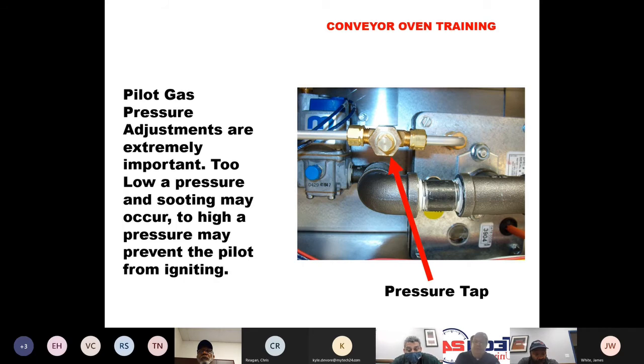Pilot gas pressure. These adjustments are very important. You're typically going to see a little T on many of the ovens where there's a tap like this that you can put your manometer on. If you have too low of a pressure, you may have sooting. And if you have too high of a pressure, it may prevent your pilot from even igniting.